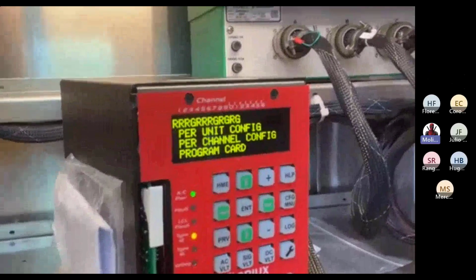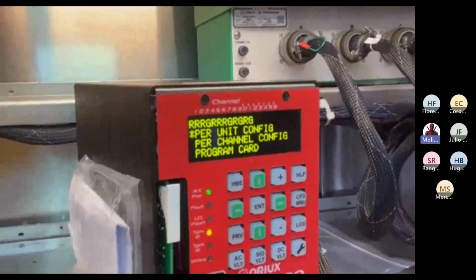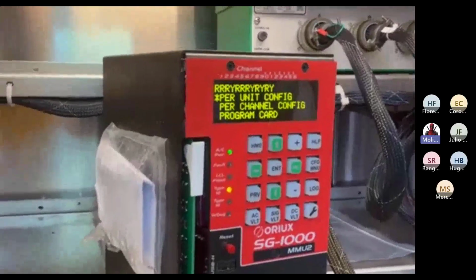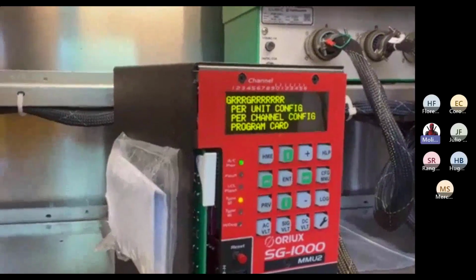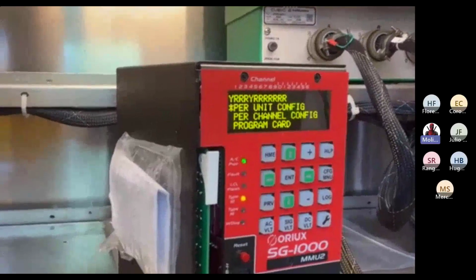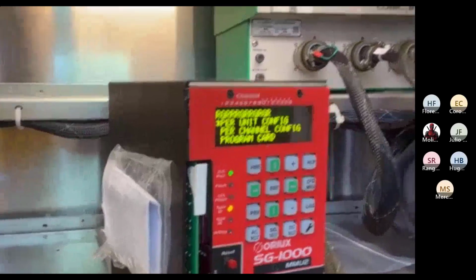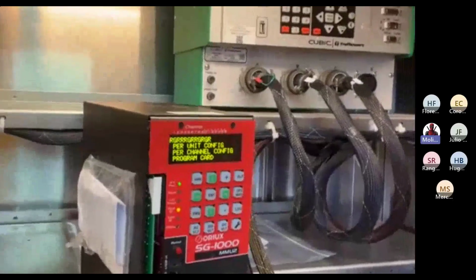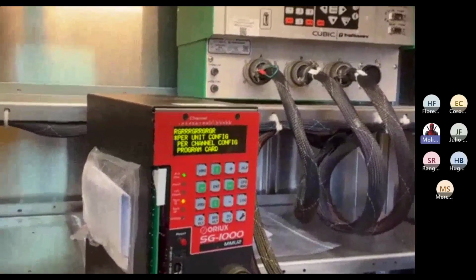Okay. So it's basically to detect. Your monitor is able to detect what kind of cabinet it's in and run in that mode. Okay, perfect. Because this is not a BIU cabinet. Exactly. So it doesn't have that type select, so it's defaulting to the type 12. Okay. Gotcha. Now you can manually go in there and change it if there's just some weird setup you have, right? But that's just what it will default to, depending on when you plug it in and power it up. That's good. I just wanted to make sure.